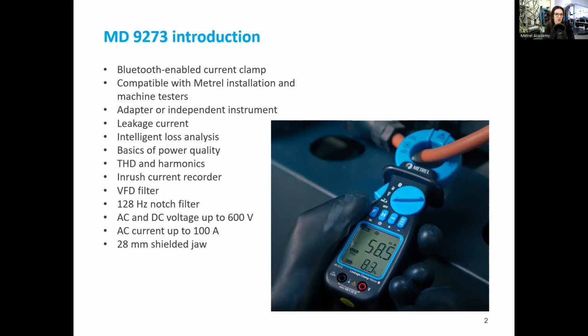We have the inrush current recorder. The inrush current can be measured as just the maximum value using only the clamps. But when we connect them to the Metrel tester, it can record a graph. The recorder sets up and it creates a graph, and it also saves the table with the data. This recording can be saved into the structure element in memory organizer and then transferred into the software as well.